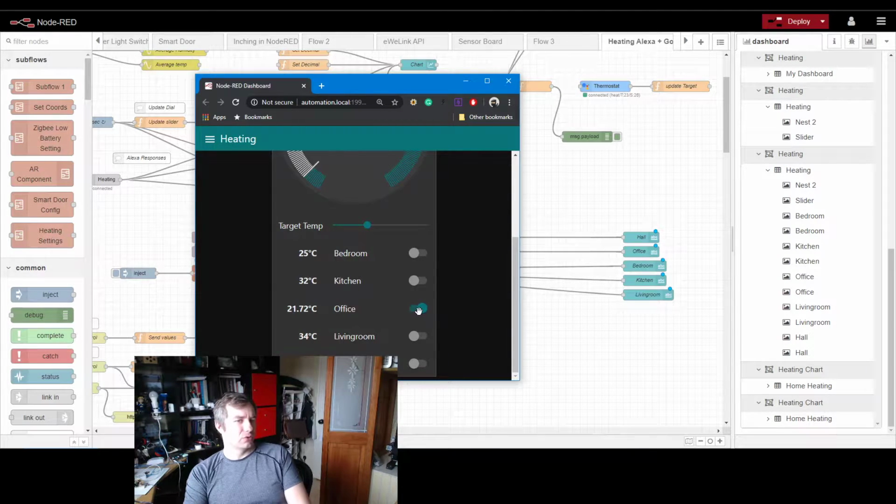So if you have 3 rooms that are active and they have the PIR sensors, as long as the rooms are set to active, let's say one is at 19, one is at 20, and one is at 21, your average is going to be 20. So it's going to keep on going until the temperature in the 3 different rooms is at the same average level, and if that's the case, then it's going to turn off the heating. Now, you could sum that.